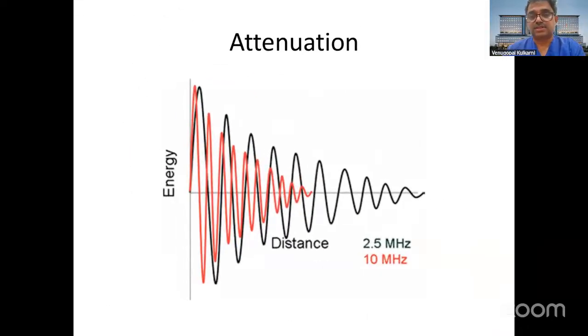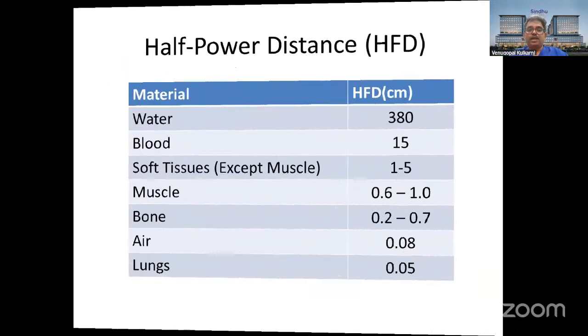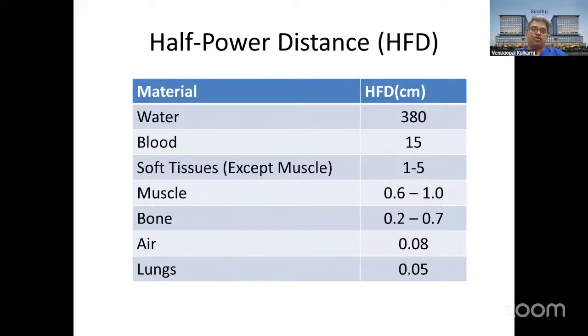As sound travels, it gets attenuated. Higher frequency attenuates quickly, lower frequency travels a further distance. If you want to scan deeper structures, we have to use lower frequencies, and for nearer structures we use higher frequencies so that the resolution is good. The higher the frequency, the better the resolution. Lower frequency has better penetration. So we have a trade-off between penetration and resolution. That's how we choose the frequency of the probe.